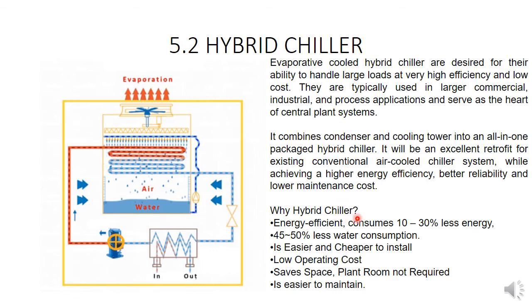Okay, why do we use a hybrid chiller? Because normally a hybrid chiller is energy efficient, and it consumes between 10 and 30% less energy, with 45 to 50% less water consumption. It is easy and cheaper to install. It has low operating costs, and it saves space because we do not need a plant room, and it is easier to maintain compared to a normal chiller.